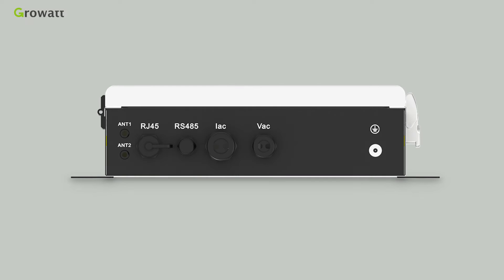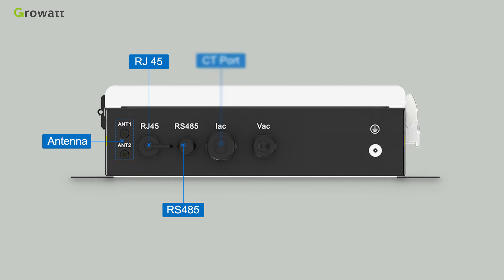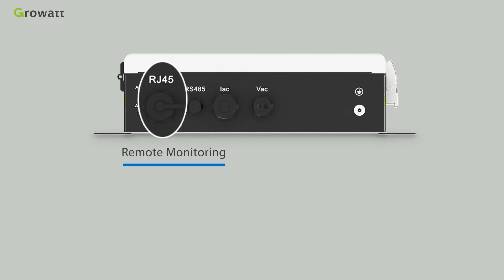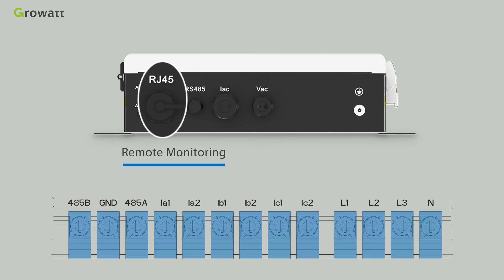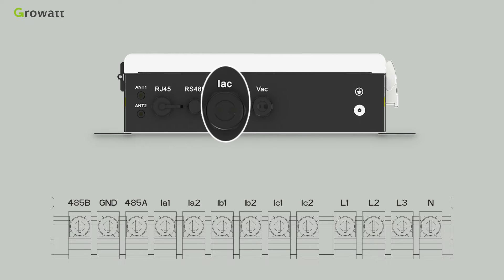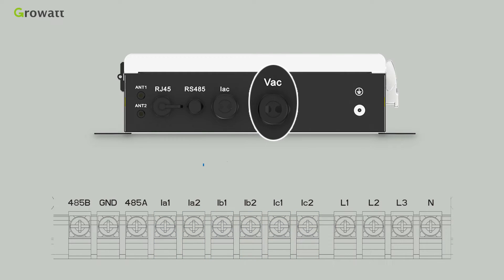The terminals from left to right are: antenna, RJ45, RS485, CT ports, voltage sampling interface, and ground terminal. The RJ45 port is used for remote monitoring. The terminal block includes 13 wiring ports. The RS485 communication port includes 485A, GND, and 485B. The IAC current transformer interface has three pairs of ports. The Vac voltage sampling interface includes L1, L2, L3, and N ports.